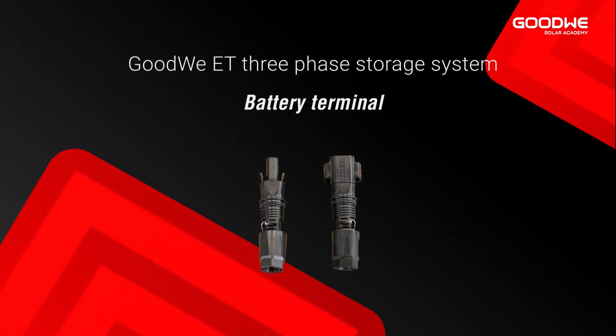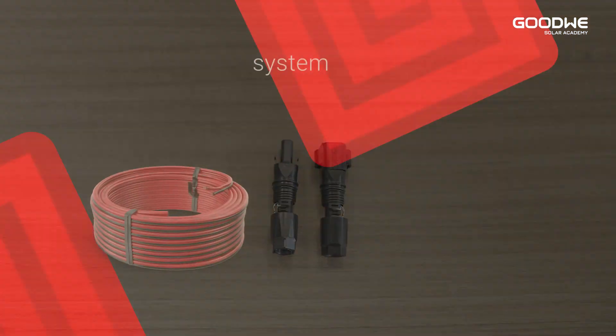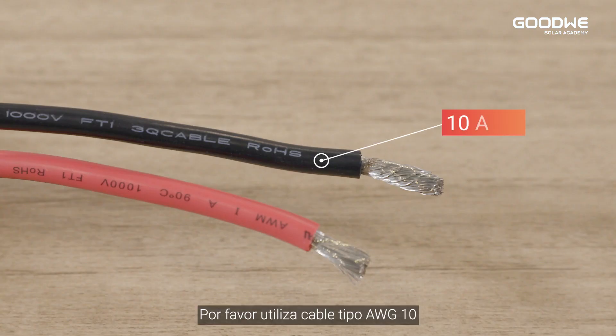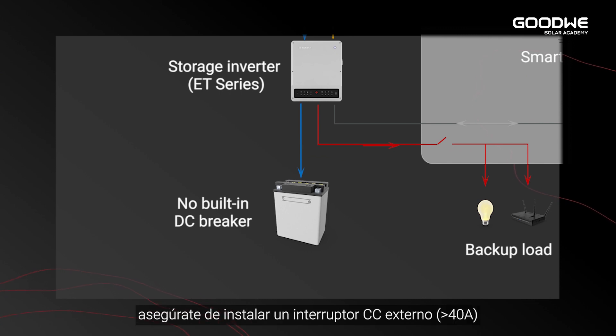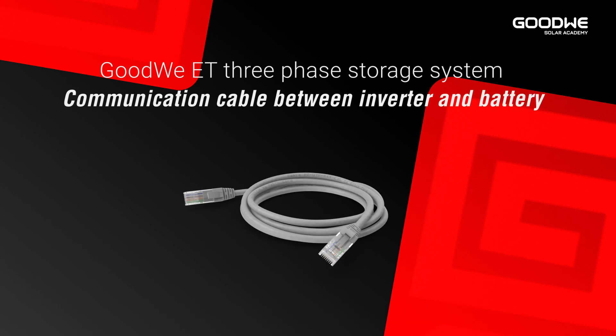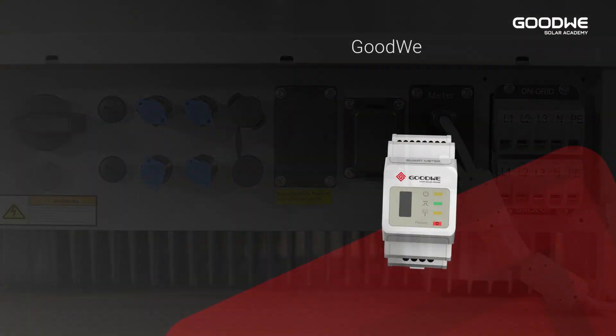Battery terminal: GoodWe provides the battery terminal in the ET accessory box. For the power cable between inverter and battery, please use AWG 10 cable. For batteries without a built-in DC breaker, make sure that an external DC breaker is connected.